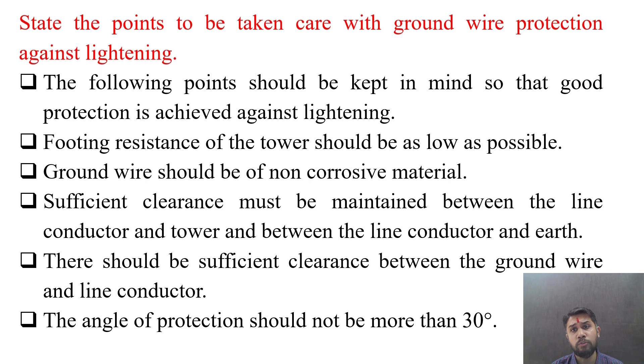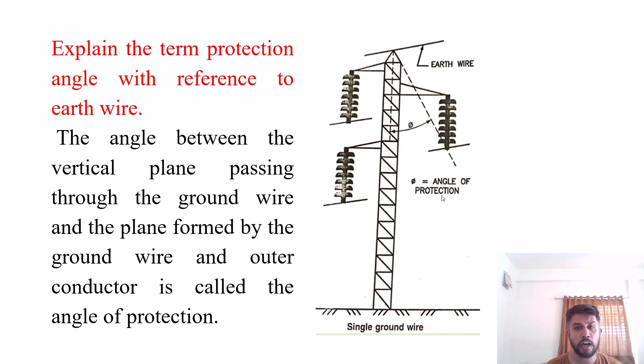strike. Explain the term protection angle with reference to earth wire. The angle between the vertical plane passing through earth wire, that is this line, and the plane formed by the outer conductor and earth wire, this angle, this line and this angle between this is called the angle of protection. This angle of protection should not be greater than 30 degrees.